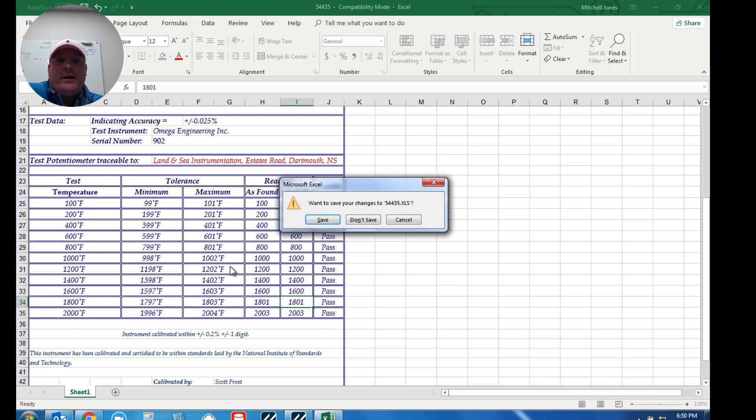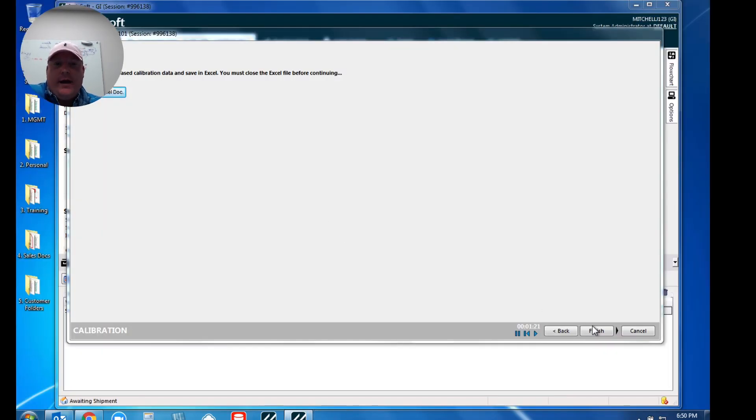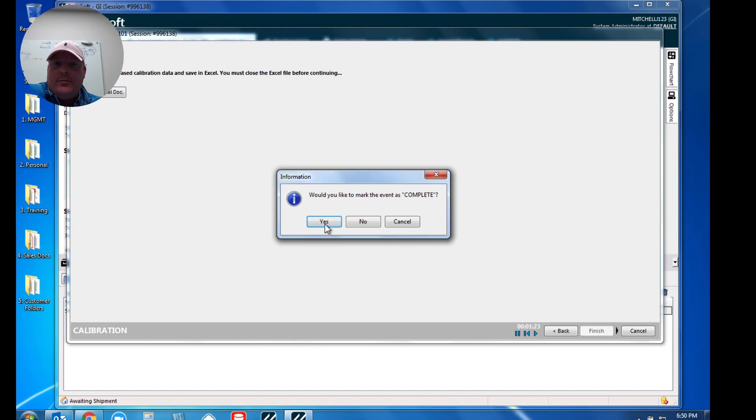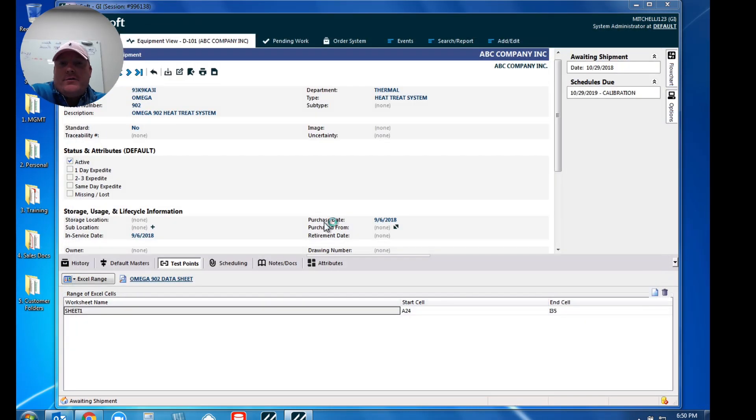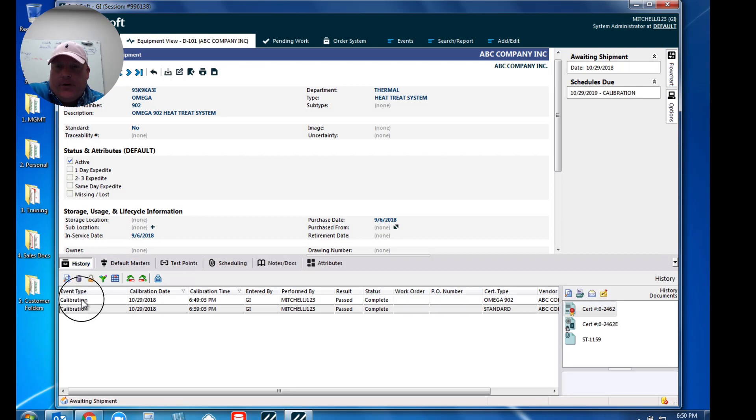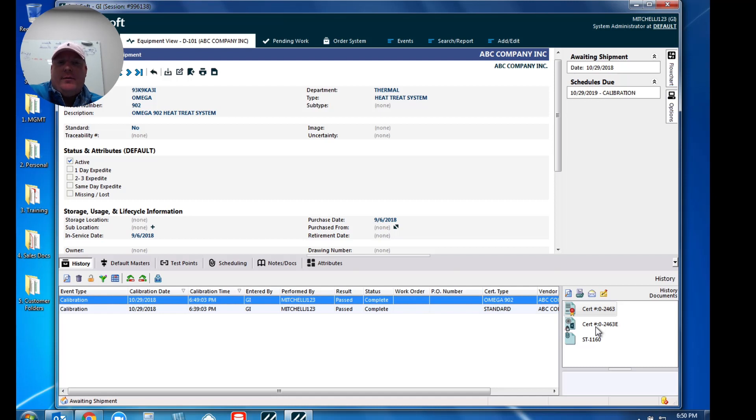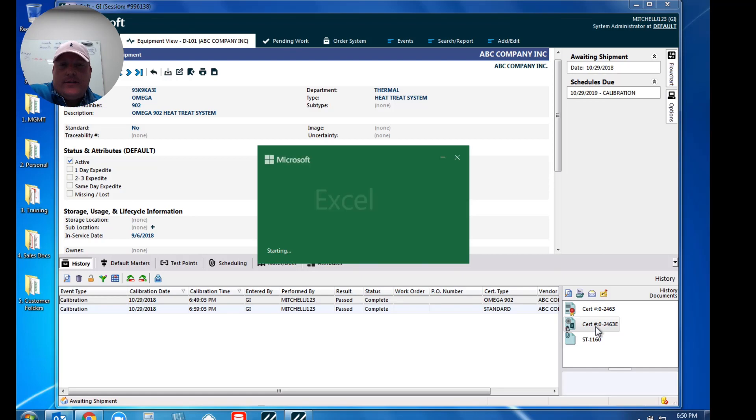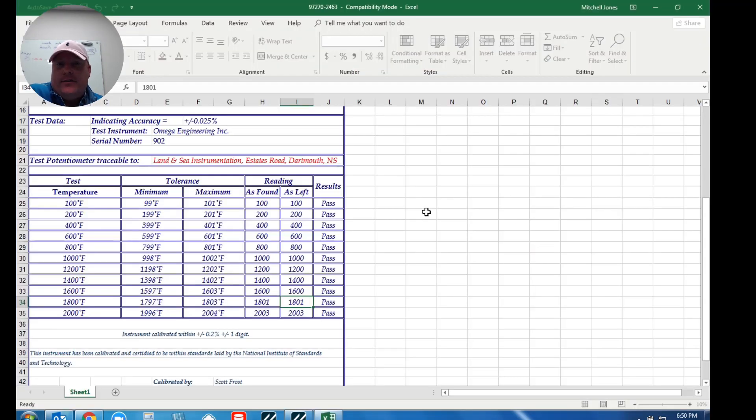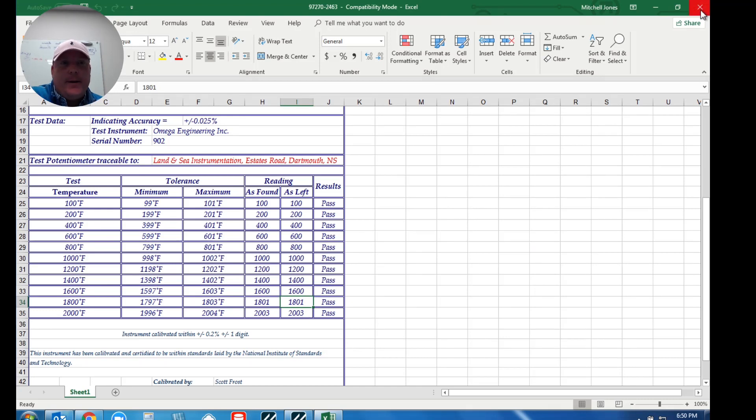So when I close this out again now, what will happen is when I hit finish and complete this calibration event, what we're going to see is if we go over to our history grid, and here's the calibration that I just performed, you'll see my certificate and then we also store a copy of the Excel file as well because we always want you to have that traceability. So if I double click on the Excel file, this is actually nothing more than a copy with the data points that we saved into that spreadsheet.